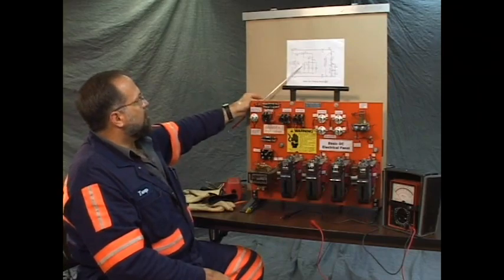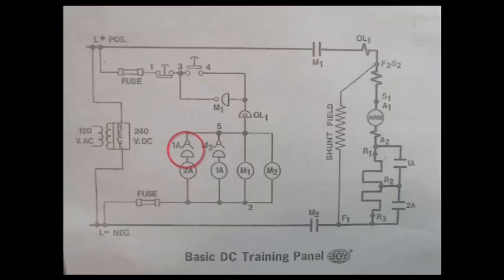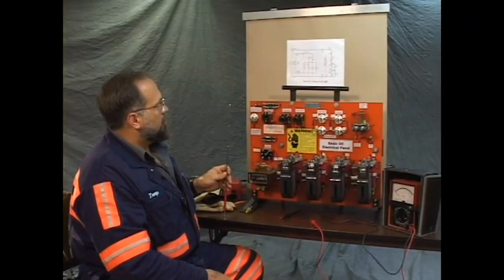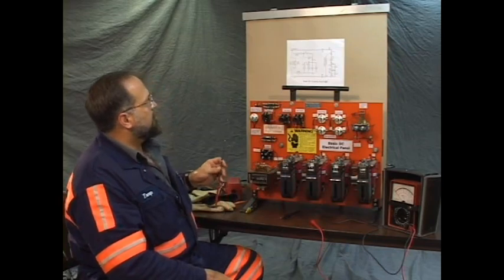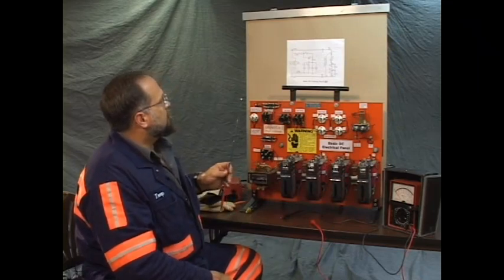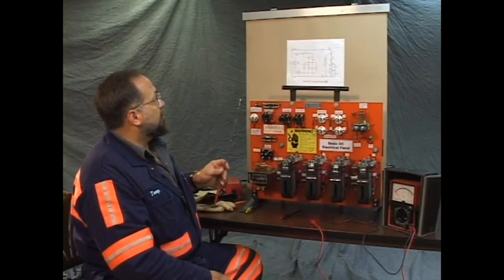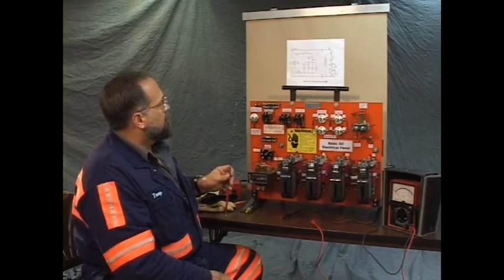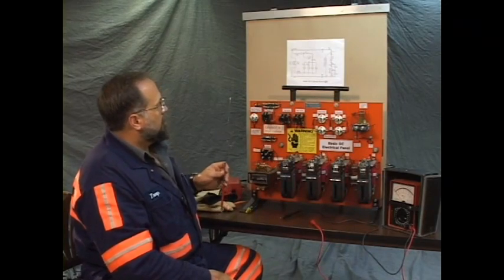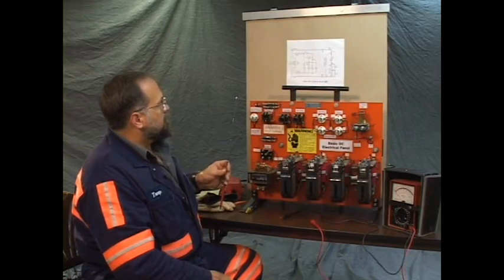We have a 1A mercury tube. The 1A mercury tube. Note the difference on the symbol, the two little wings on the side. Those designate that as a normally open, timed closing mercury tube. And I have an M2 mercury tube, which is also normally open, time closed. Right there. These are very old type timers, but they're pretty reliable actually. They're not used much anymore, but they arrange for the proper sequence of contactor closing.